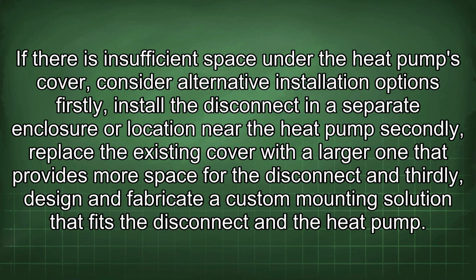If there isn't sufficient space under the heat pump's cover, consider alternative installation options. Firstly, install the disconnect in a separate enclosure or location near the heat pump. Secondly, replace the existing cover with a larger one that provides more space for the disconnect. And thirdly, design and fabricate a custom mounting solution that fits the disconnect and the heat pump.